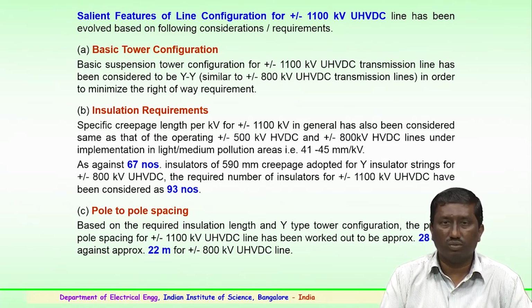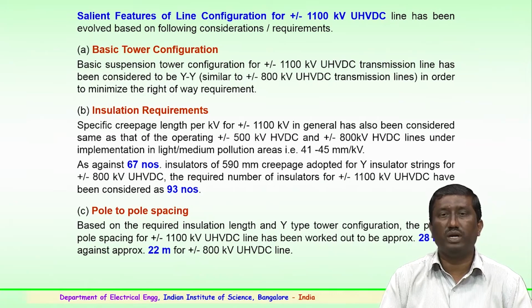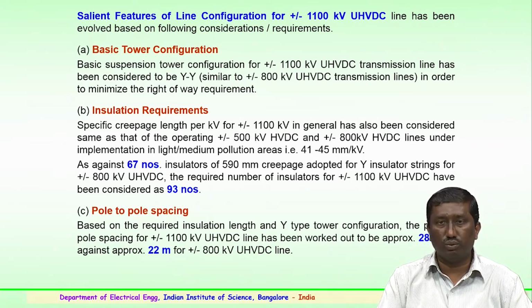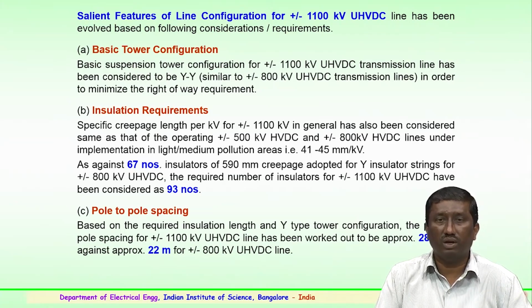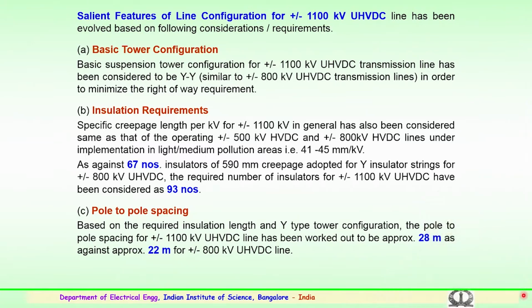Second is insulation requirements, very important. The specific creepage per kilovolt for plus minus 1100 kV has to be considered the same as that of plus minus 500 kV DC or plus minus 800 kV lines, which are under implementation in different pollution zones, light and medium areas, normally assumed to be 41 to 45 mm per kV in case of medium or light pollution. Here 67 insulators of 590 millimeter creepage are being used for Y type insulator strings for 800 kV. In case of 1100 kV you may have to use 93 insulators. So, the number of insulators will increase, and the clearances will increase.